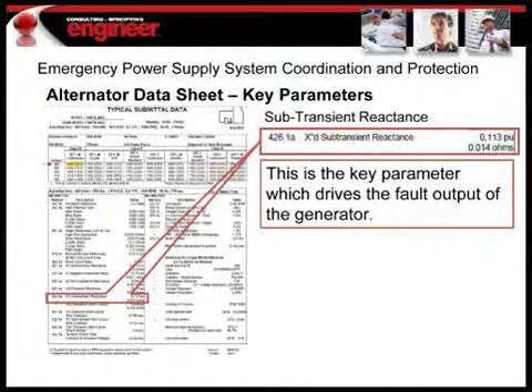The final major value is the subtransient reactance, and X double prime d is what it's identified as. This is an important parameter. It basically is tied to the first 5 cycles or so of the generator performance, which is your fault output of the generator. And it's put in per unit value, so it's not a straight number. It's based upon what the generator kW is and all that.